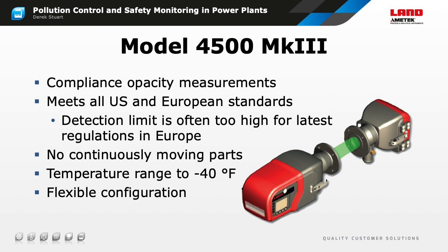It's designed for the highest reliability in the harsh conditions associated with stack-mounted instruments. It has NEMA 4X sealing, a temperature range from -40 to +55 Celsius, that's -40 to +130 Fahrenheit, and the only moving parts are the calibration motors, which are activated for a few seconds each day while the instrument performs its automatic zero and upscale checks.